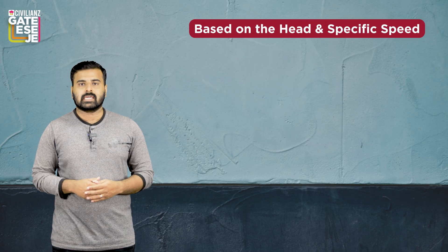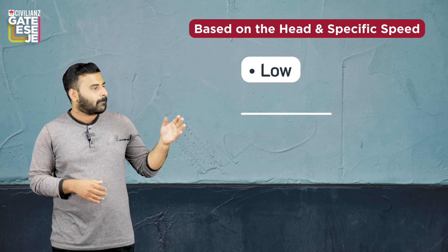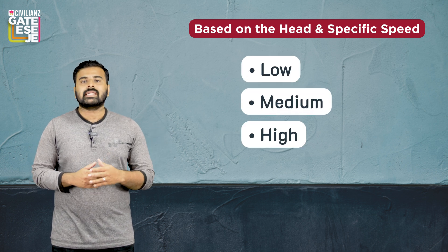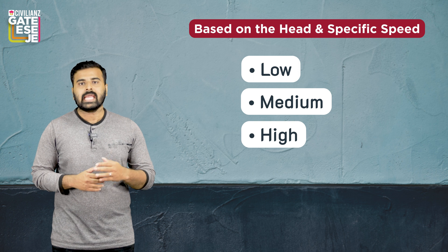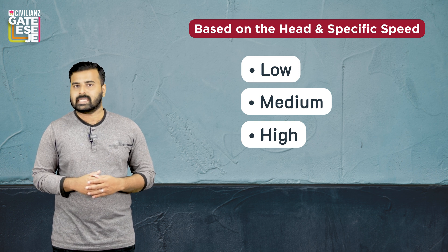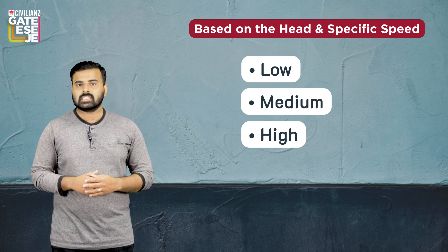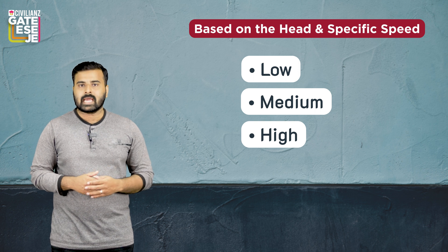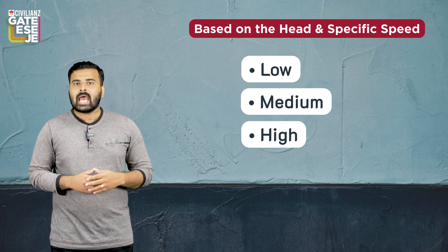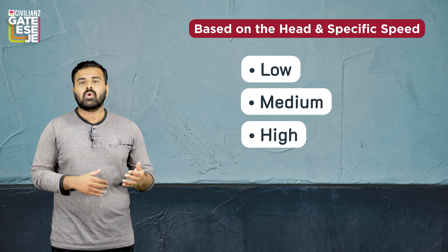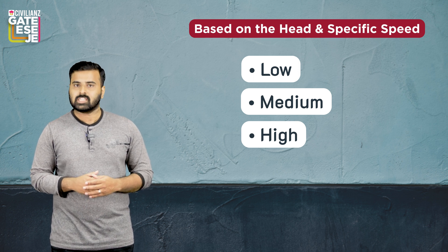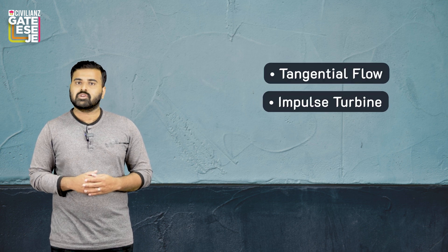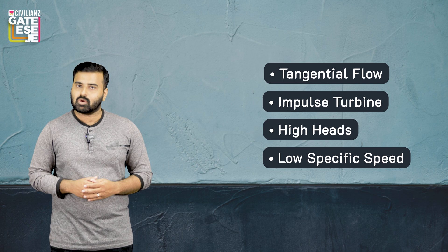Based on specific speed and head, turbines are generally classified into three categories: low, medium, and high. A Pelton wheel is preferred when high head and low specific speed is required. A Francis turbine is used when medium head and medium specific speed is required. Kaplan and propeller turbines are preferred when low head and high specific speed is required. So in short, the Pelton wheel is a tangential flow impulse turbine used for high heads and low specific speeds.